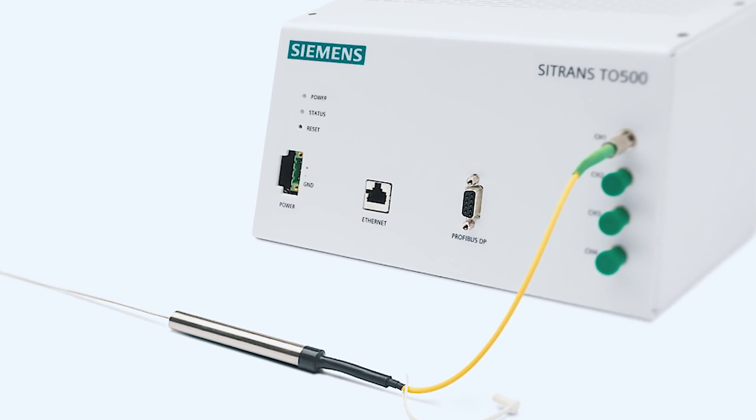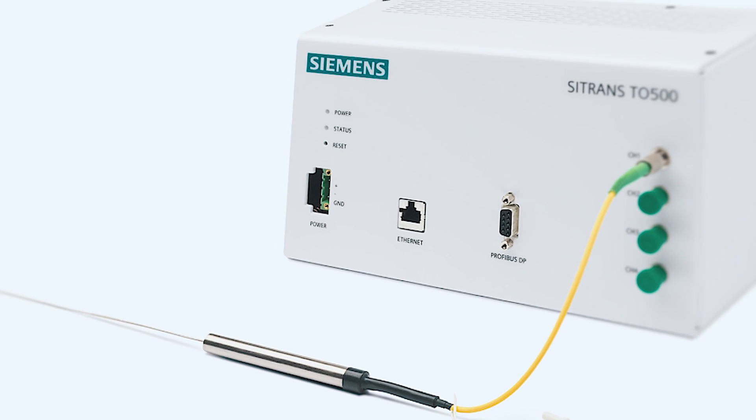Gratings written on the fiber-optic serve as sensor elements. Regardless of the number of sensors, the diameter of the measuring probe is always less than two millimeters. This also reduces the diameter of the protective tube.